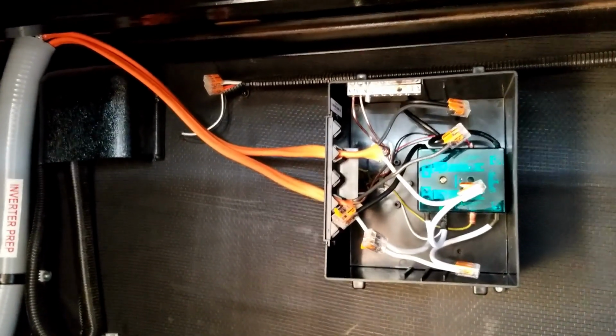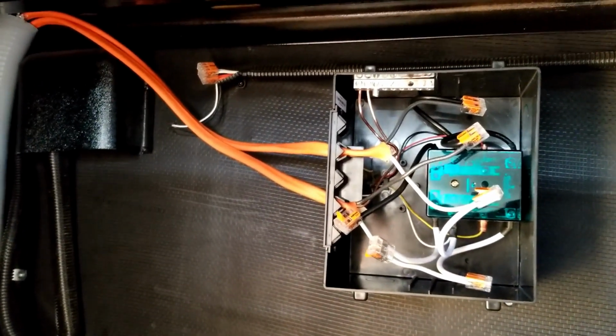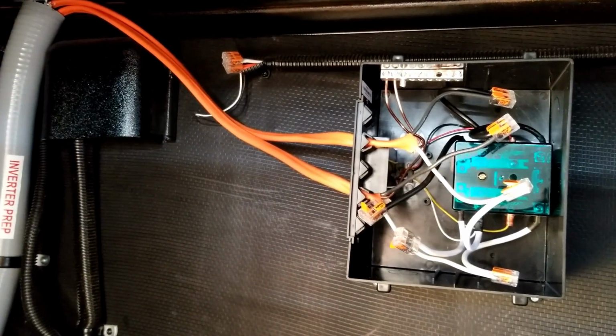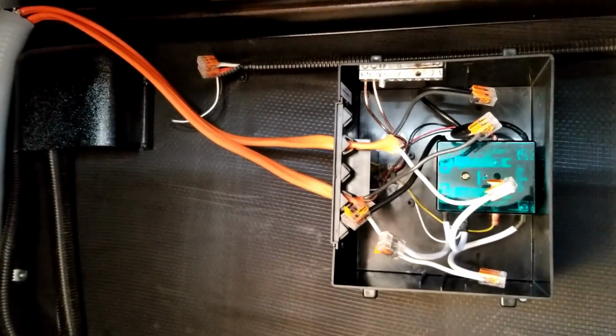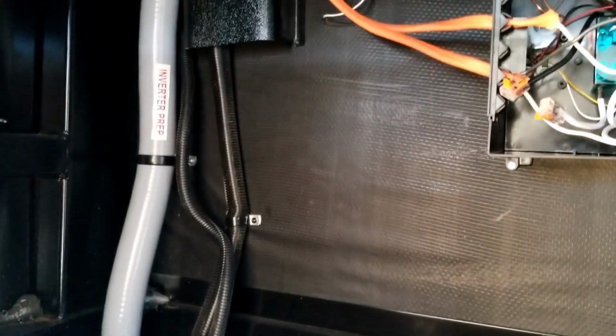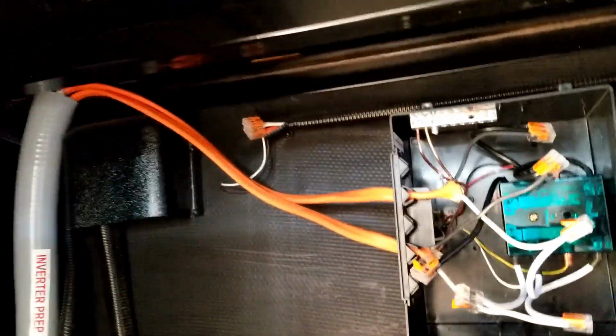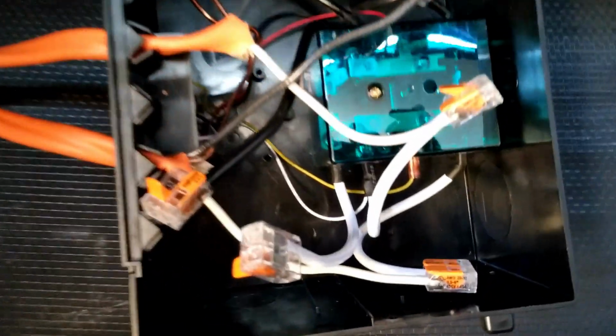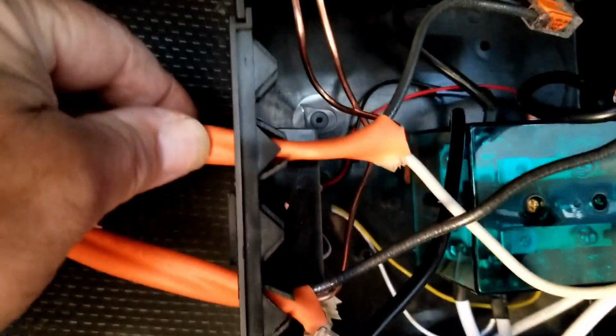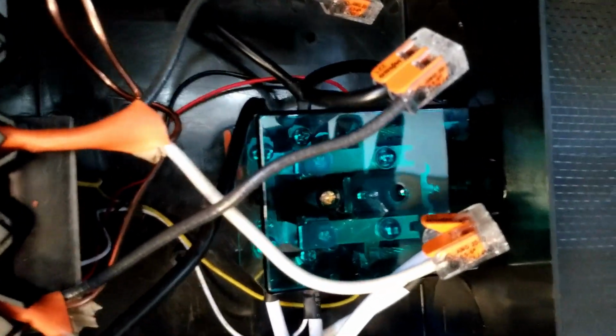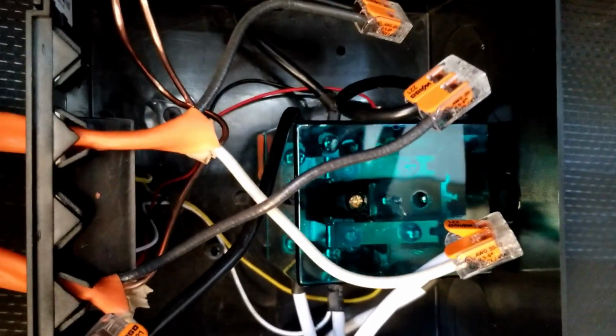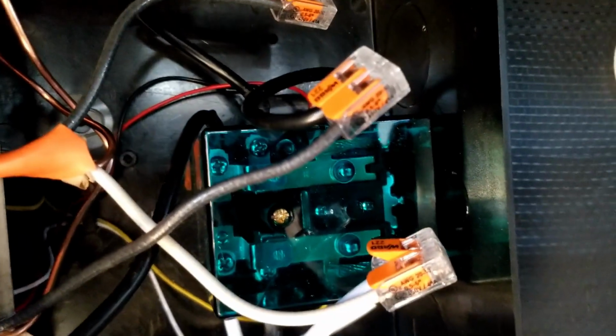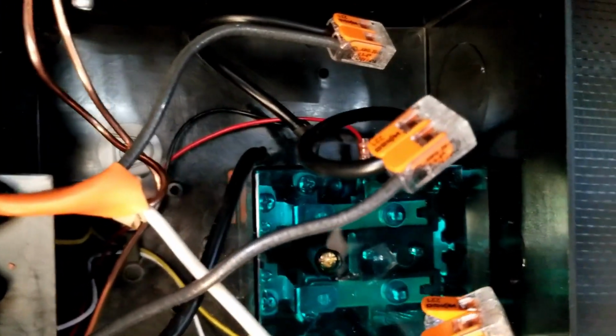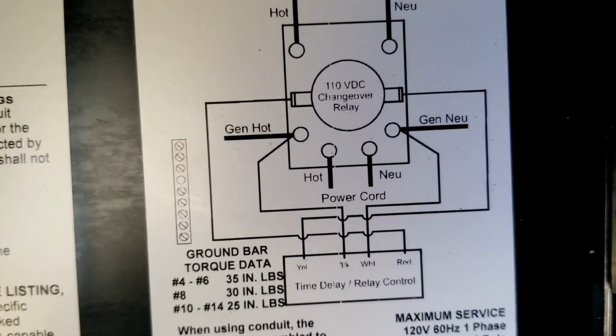With the automatic transfer switch temporarily mounted, the final resting place will be somewhere different, so I didn't want to cut off any of the Romex until I figure out where that's going to be. If you remember, this top wire was coming from our panel with the 30 amp 120 volt circuit. It's tied into the circuit that they call for the generator.